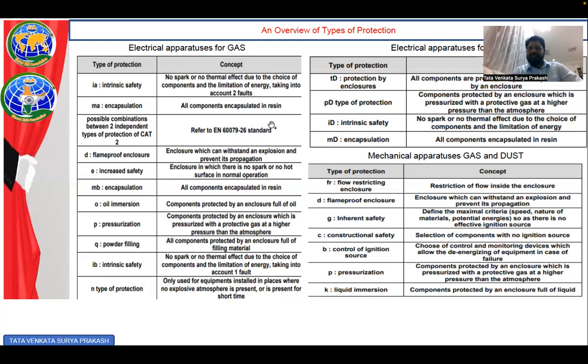Similarly, for mechanical apparatus for gas and dust, we generally recommend flow restricting enclosures, which restrict the flow inside the enclosure itself so that an explosive environment externally will not form and is contained internally. And for flameproof enclosures, we recommend enclosures which can withstand an explosion and prevent its propagation. So these are the different types of protection that we will recommend for each equipment or apparatus used in explosive atmosphere environments.